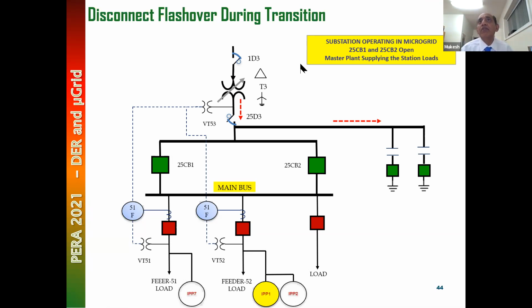Now all the repair work was finished. We are going to restore. We are just going to close the system back without causing a customer outage. We're going to synchronize these things back to the system. We're going to close all these breakers with a sync check and synchronization. That was the plan. So what happened? This transformer does not have a breaker. They have disconnect switches.